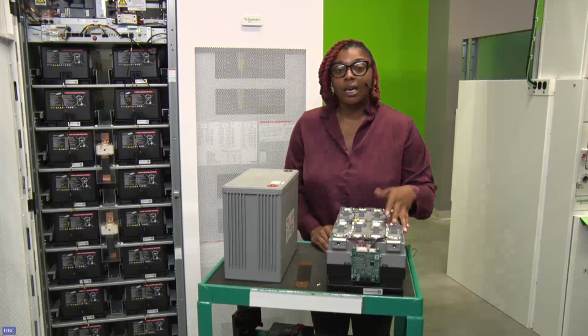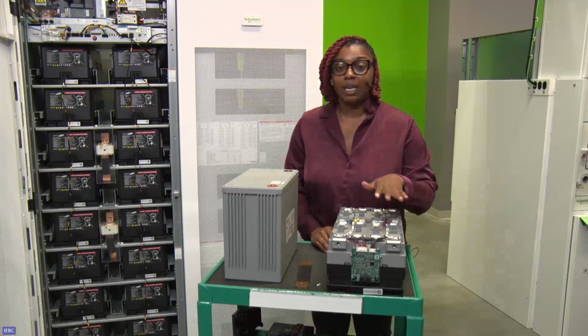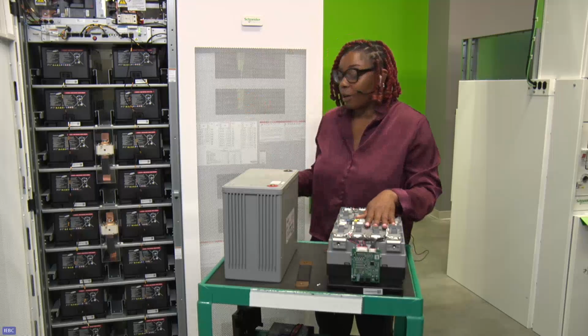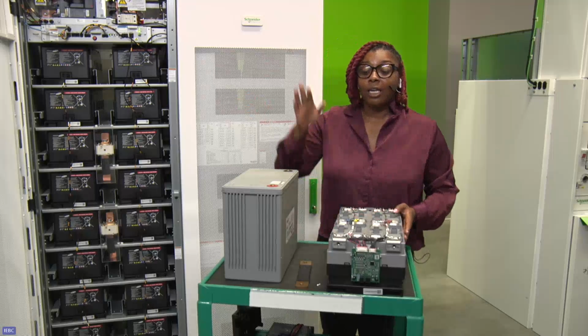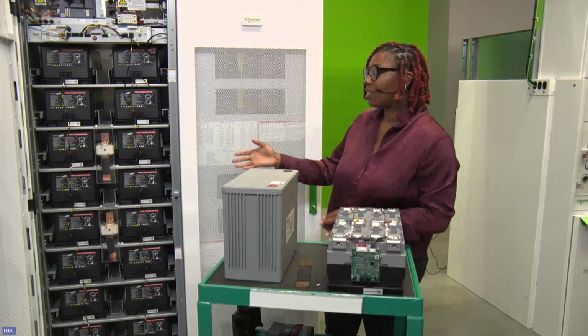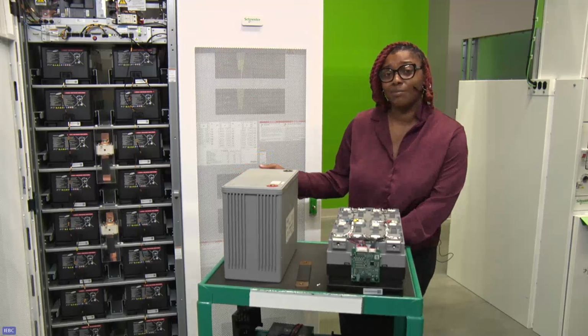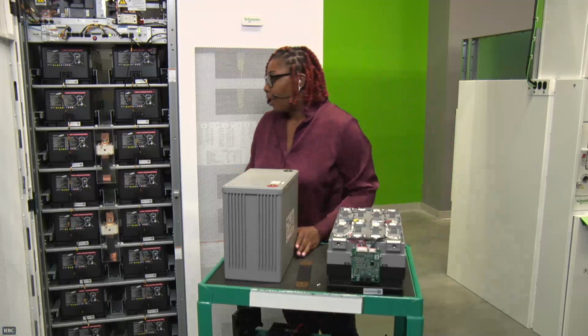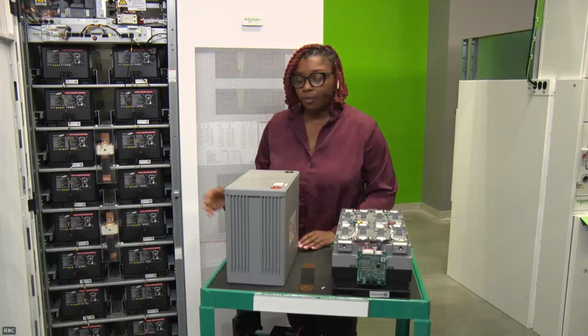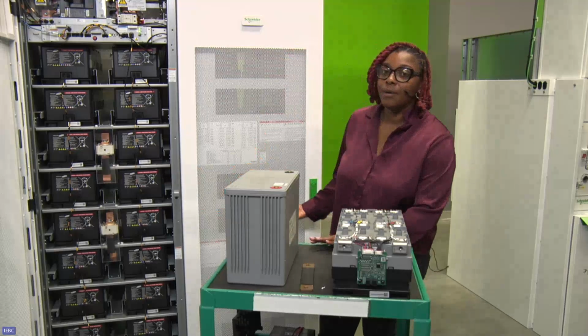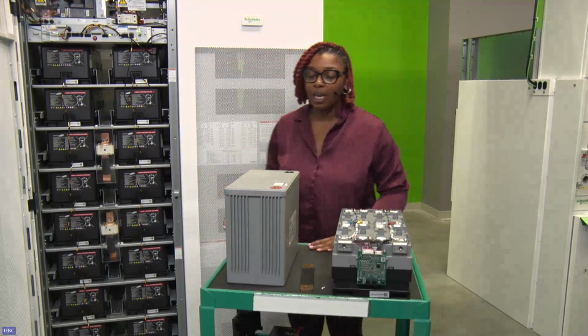So when we're looking at that 0.3 voltage difference, that is cell to cell, not battery to battery. So one bad battery, the entire cabinet goes down. Each of these batteries gives about 5 to 6 minutes of runtime, and you can get as much runtime as you need by just adding more battery cabinets.